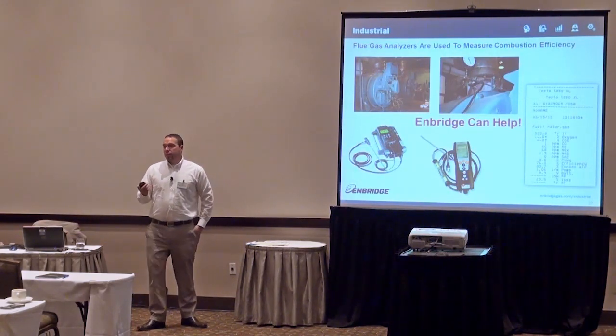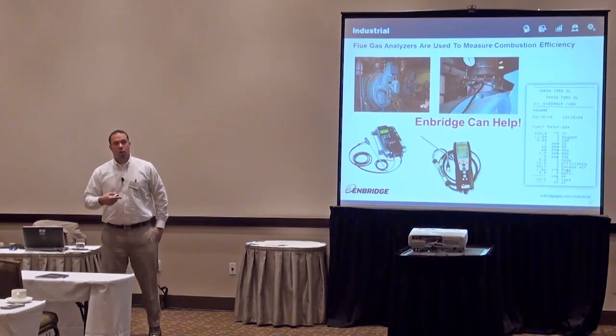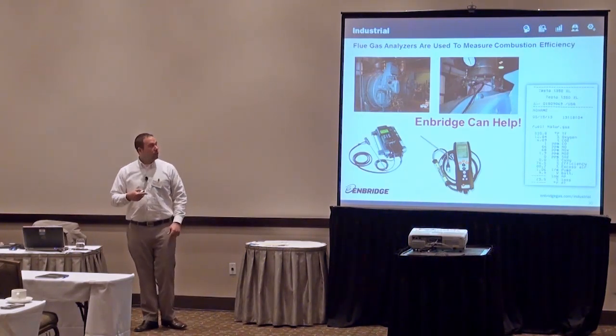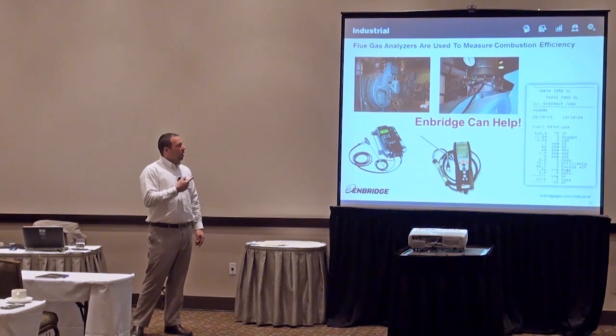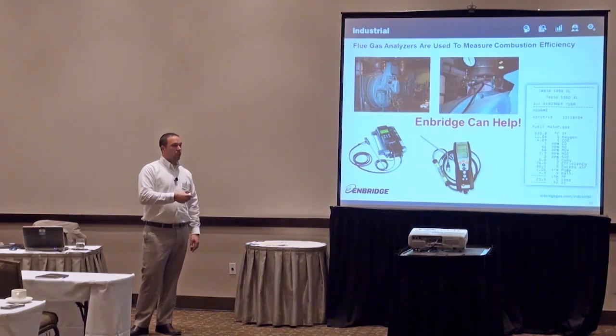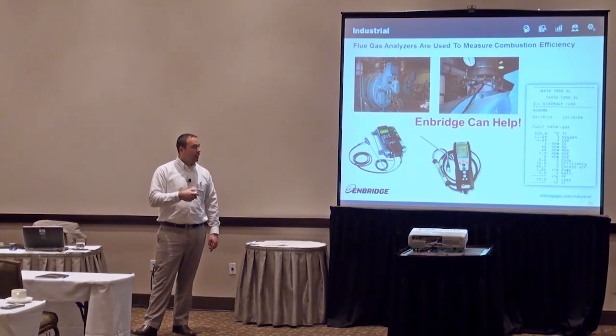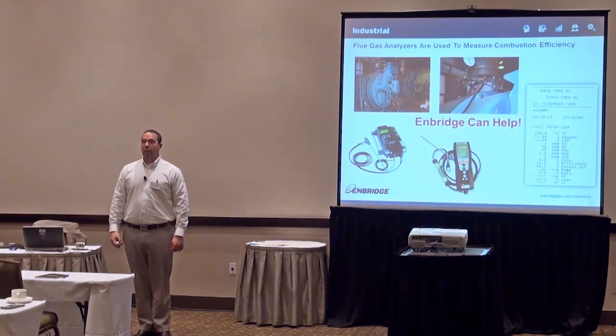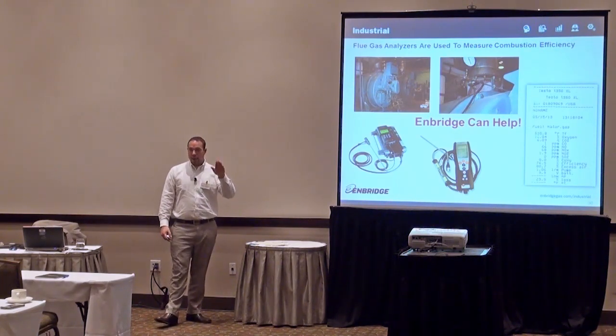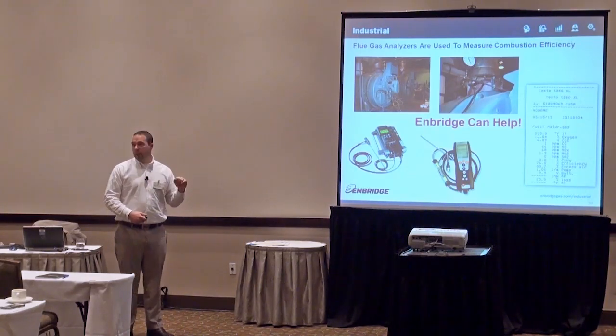Typically, you guys are having maintenance suppliers come in and do this for you. We can also support if you don't know where you are and need to understand where you are for moving forward in terms of energy efficiency improvements. This is where a Flue Gas Analyzer, which we have, we can come in and look at your boiler and produce that strip for you. So we can go in, work with you. You need about a 1/4 inch hole in your stack, and we slide the Flue Gas Analyzer in, and ideally we move through the firing range, so sort of the gas pedal of the boiler, and take the efficiency readings. Is that clear?